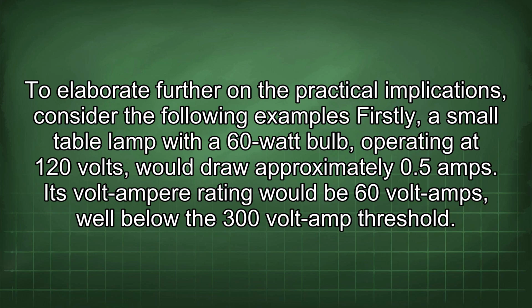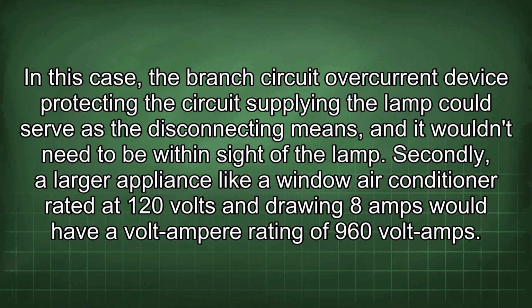To elaborate further on the practical implications, consider the following examples. Firstly, a small table lamp with a 60-watt bulb operating at 120 volts would draw approximately 0.5 amps. Its volt-ampere rating would be 60 volt-amps, well below the 300 volt-amp threshold. In this case, the branch circuit overcurrent device protecting the circuit supplying the lamp could serve as the disconnecting means, and it wouldn't need to be within sight of the lamp.